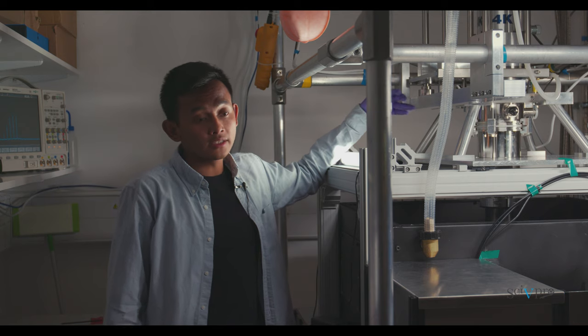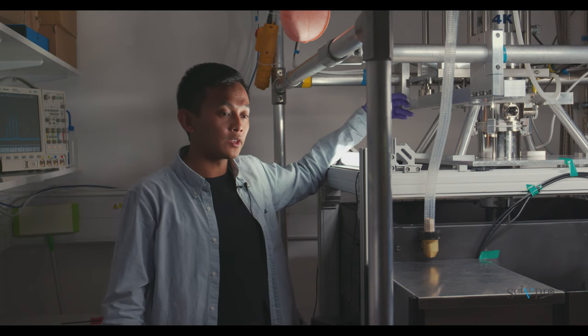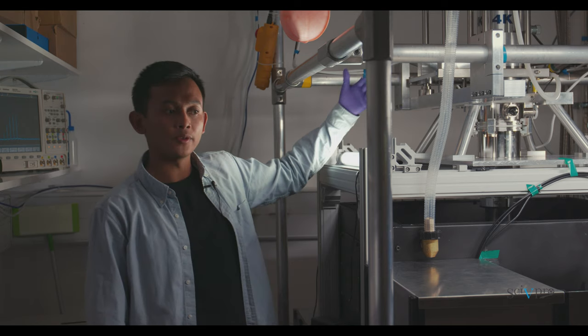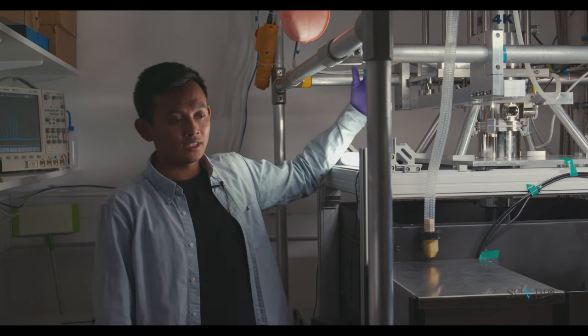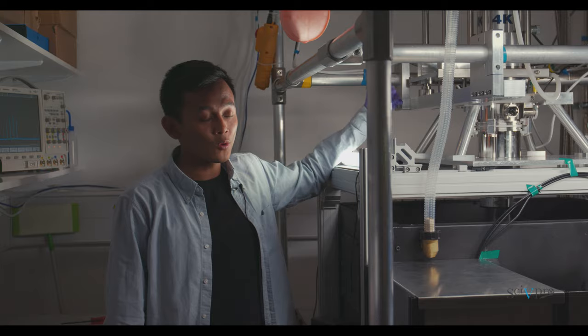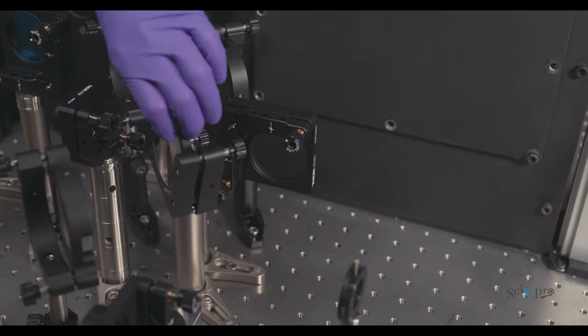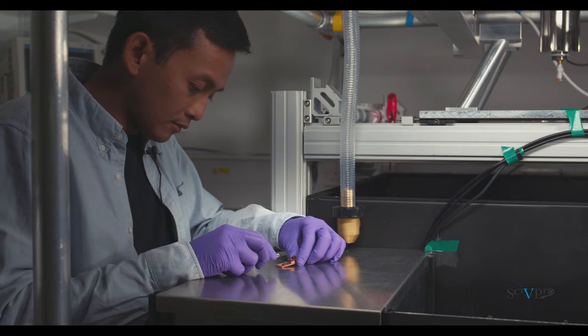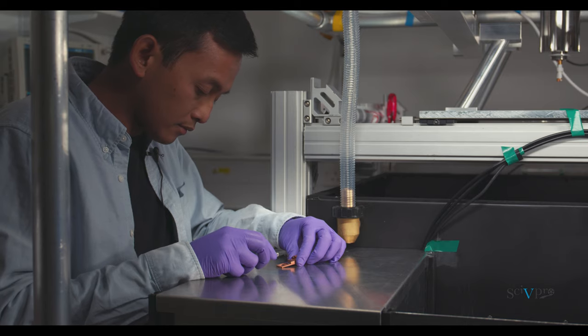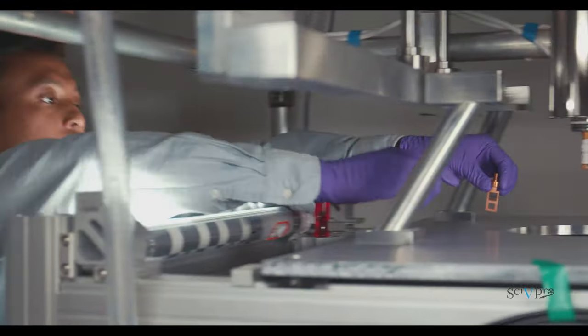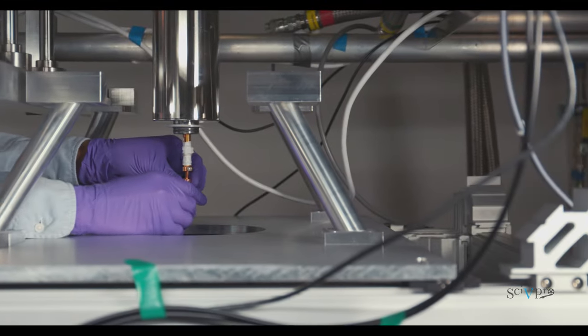We have our standard trace that indicates that our setup is working well using this cobalt platinum. So prior to measurement, we put the sample, and if the trace is lower than what we expect it means something goes wrong, and mainly it's because of misalignment. Make sure the setup is configured in emission mode. Mount the sample on the sample holder. Mount the sample holder on the cryostat.